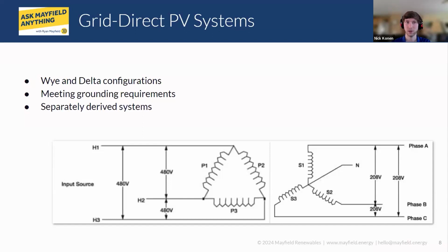Functionally for the transformer, usually in your PV applications, you only really need that delta there on that grid facing side. Touching back on what Jeff was saying there, with it being an isolation transformer, it creates a new separately derived neutral on that inverter facing side for that balanced reference there that the inverters like to see, or typically the PV inverters like to see.